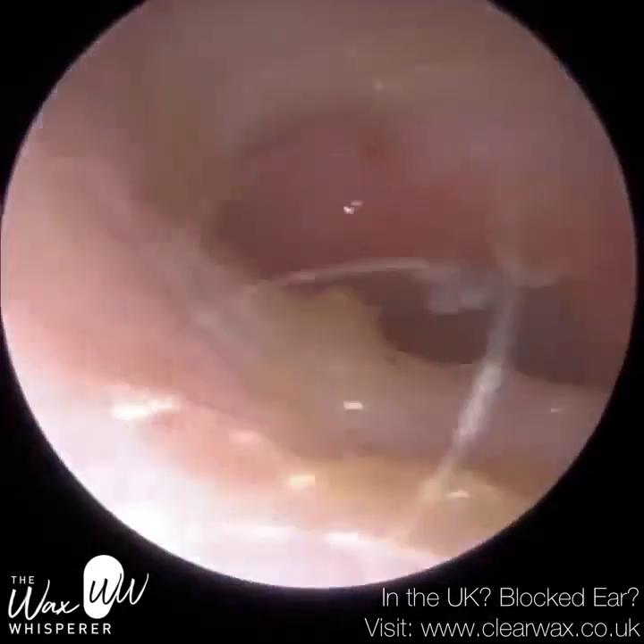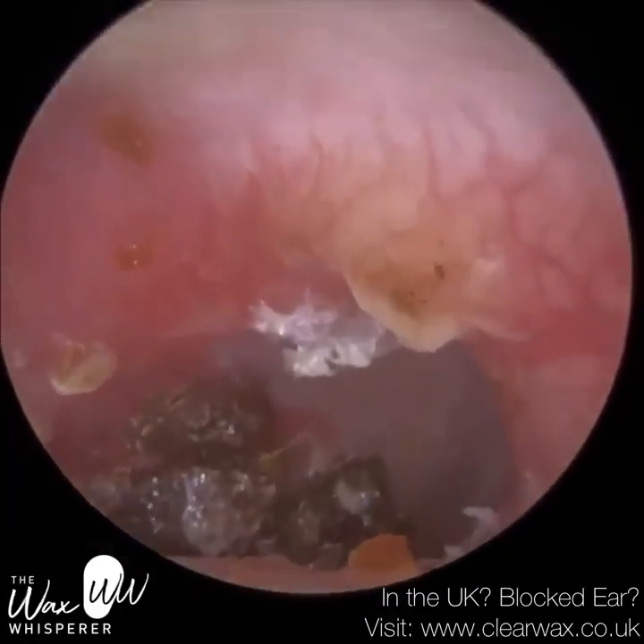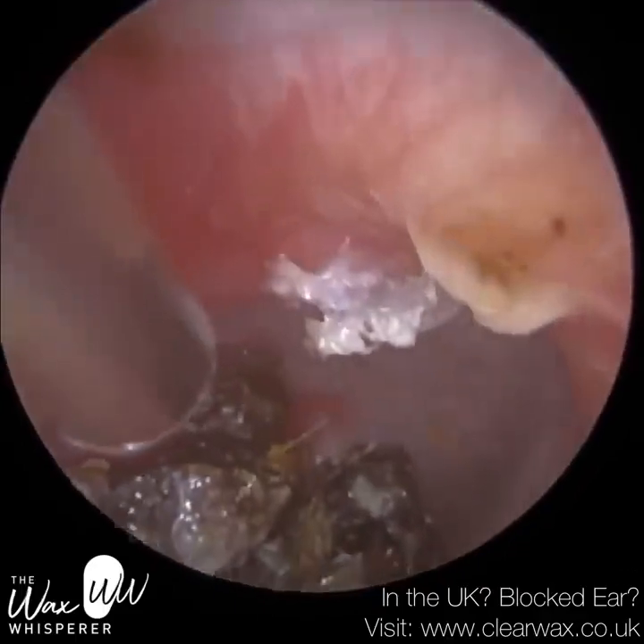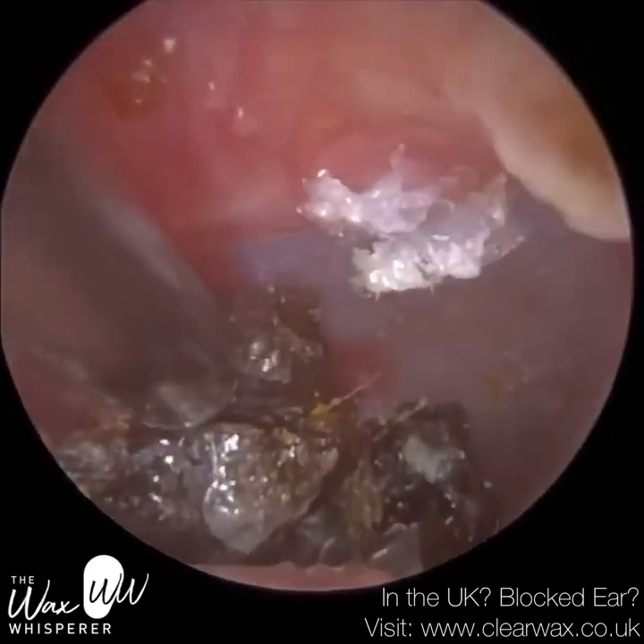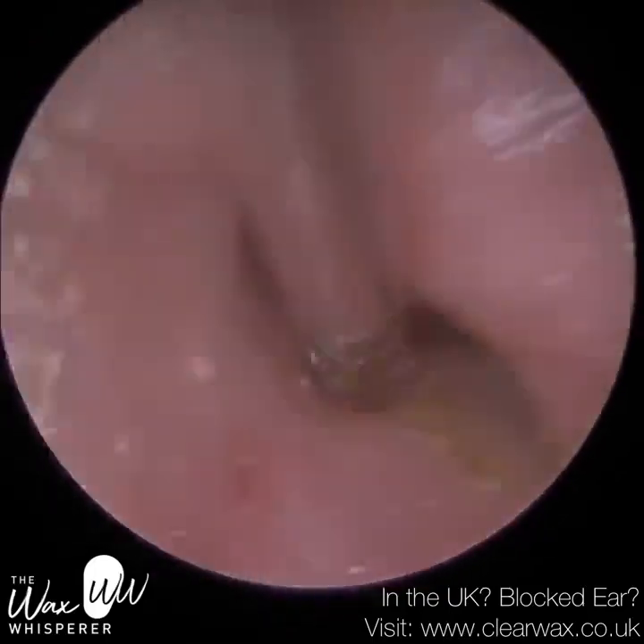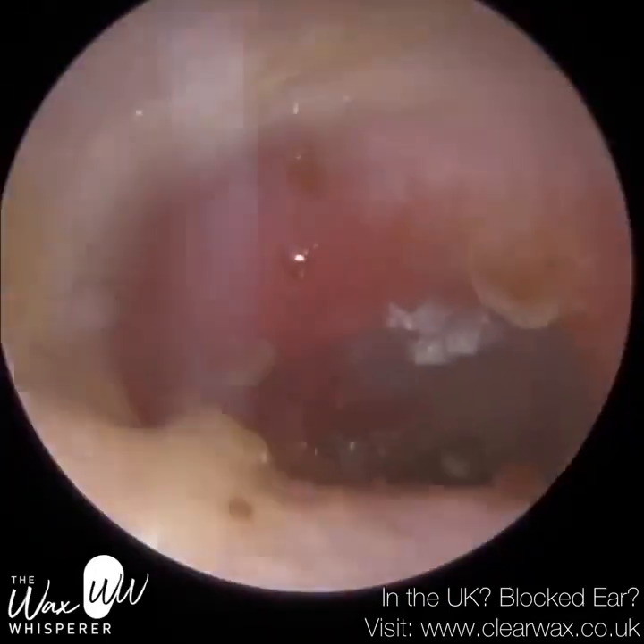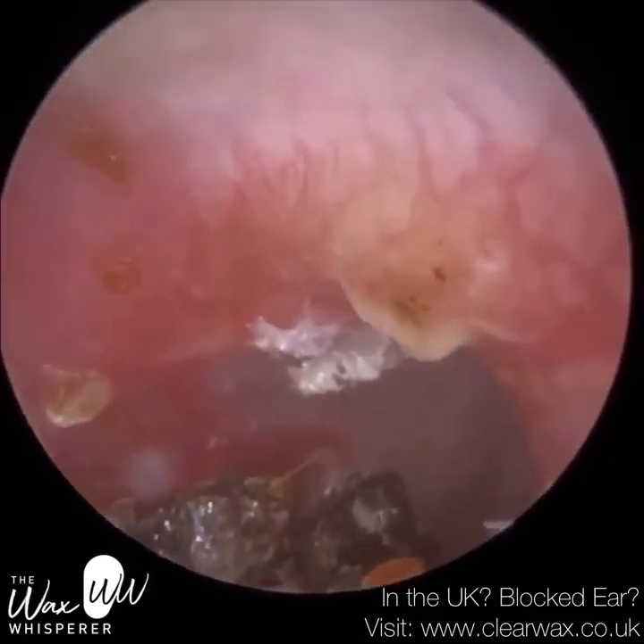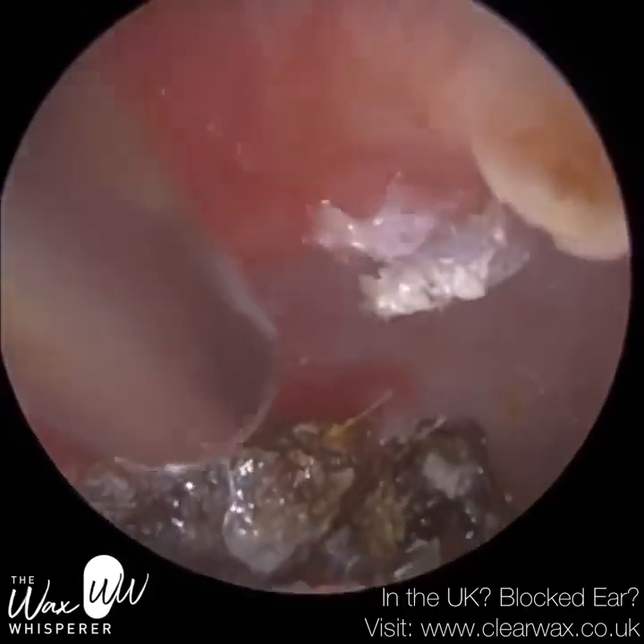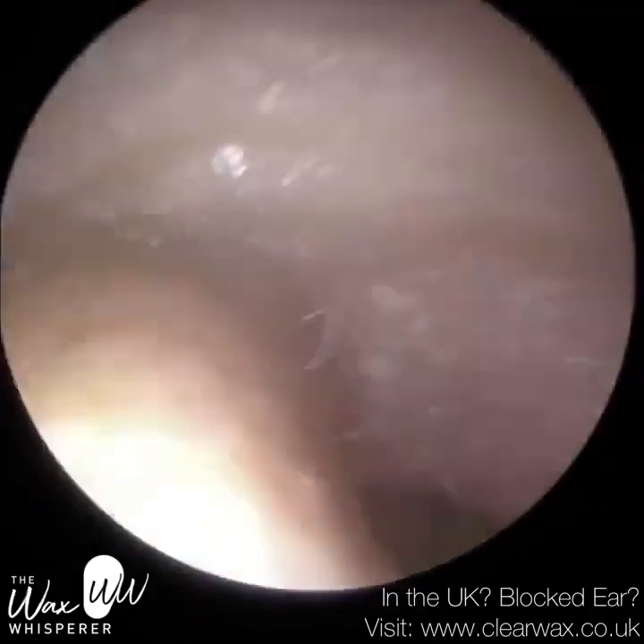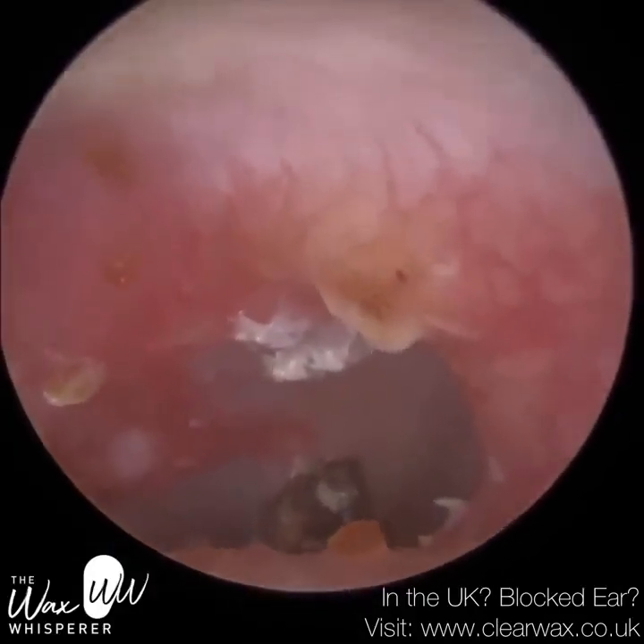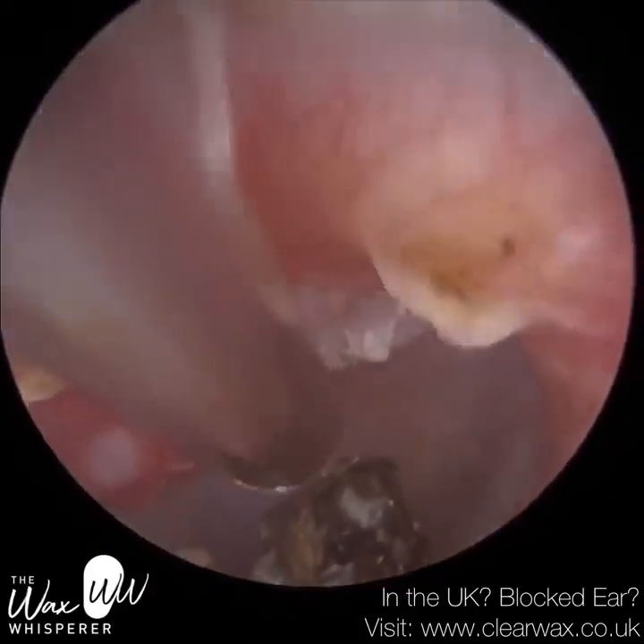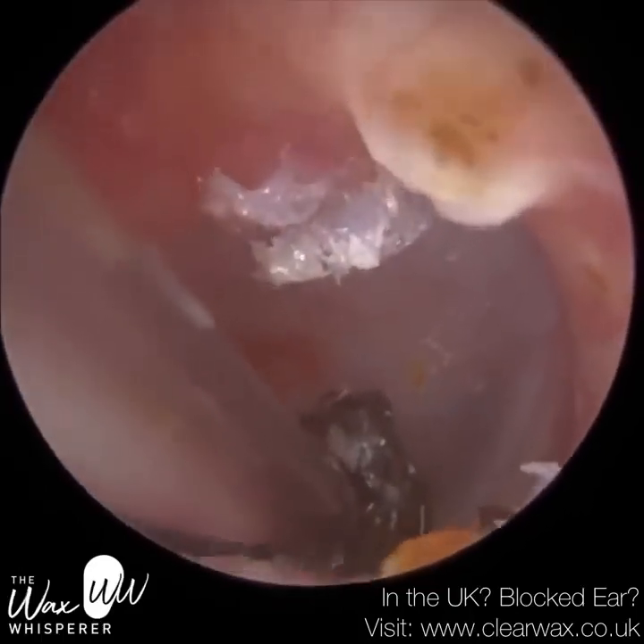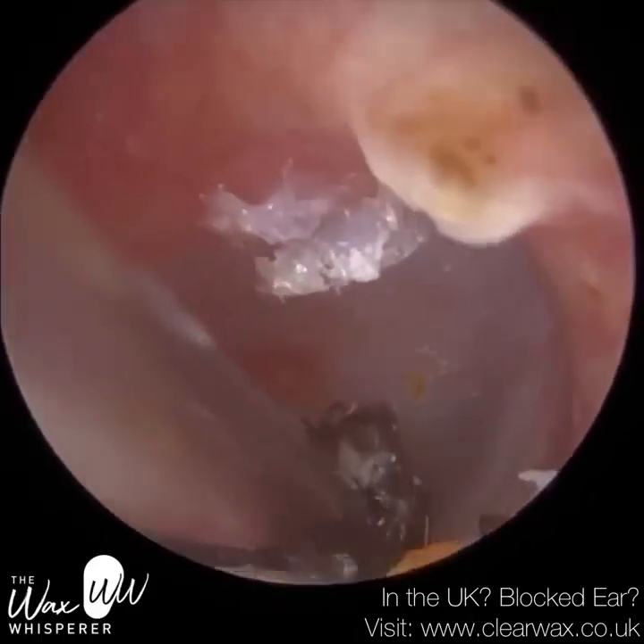This technique also ensures the instrument is inserted into the ear completely safely. It's not in close proximity to the canal wall, so it's not going to hurt or cause any trauma to the patient as you're inserting it. If you just stretch the ear open and try to force the instrument in blindly, you're going to bump into the canal wall. So once the endoscope's into the ear and you're using the instrument to push the cartilage that's covering the tip of the endoscope away so that it reveals the tip of the endoscope, you can then glide the instrument over the top of the endoscope, which means when it comes into the ear, it's going to be in the middle of the ear canal.